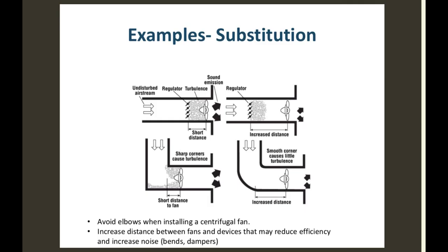But the deal there is that as you increase that velocity, there's more friction inside the ductwork, and you're going to generate more noise. Not only that, but when it gets to the end, when it comes out of the device and it's got to go across the room to that other side, if you have a dead end up there in a 90 degree right angle, that air is going to blow up there, hit that ductwork, blow across, and make a lot of noise as it creates friction, noise and heat, as it hits that. If you had a gentle curve, the bigger the radius of the curve is, the less noise you're going to generate.